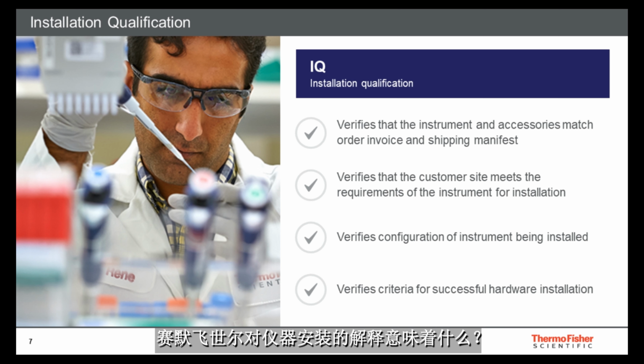What does Thermo Fisher Scientific interpret this to mean for the installation of instrumentation? It means we will verify and document instruments or equipment against order invoices, any site requirements specific to the instrument or equipment, any configuration details of the instrument or equipment, and any specific installation criteria. It should be noted that the IQ, or installation qualification, is not repeated once the instrument or equipment is successfully installed. Follow-on qualifications would be an OQ-PQ.